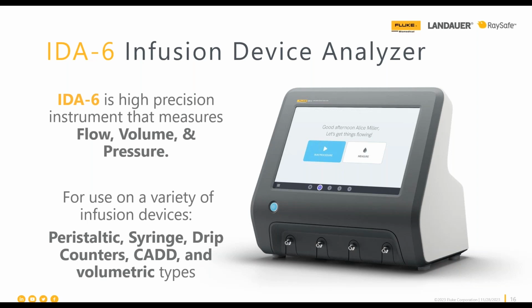Great overview on infusion pumps themselves. Now, I just want to spend a few minutes to highlight some of the key features that differentiate IDA-6. And then as we get into the demo portion, you'll be able to see this in action. But first, just as a high-level overview, really the IDA-6 is an infusion device analyzer. It is a precision instrument that examines the performance of the medical infusion devices and measures the flow rate and volume supplied, as well as the pressure generated. And with the IDA-6, you can test up to 4 pumps at the same time.